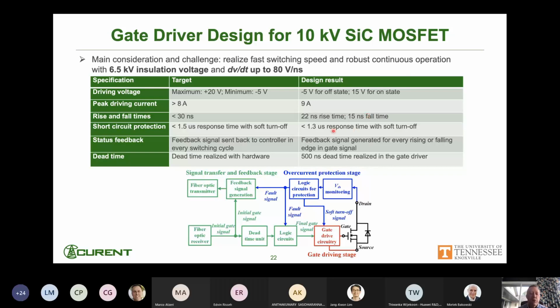Our short circuit protection, based on looking at the withstand capability of these 10 kV, 20 amp devices, we wanted to be less than 1.5 microseconds. And so we ended up at about 1.3 microseconds.